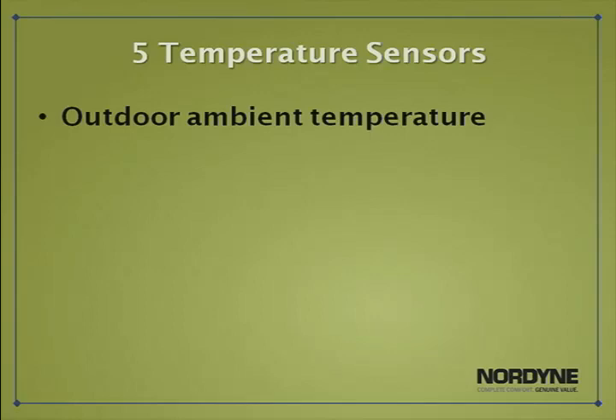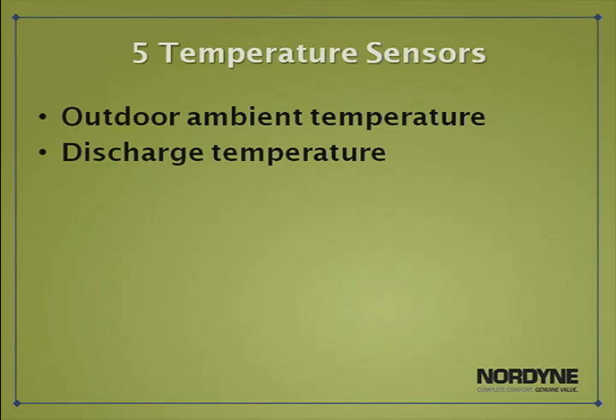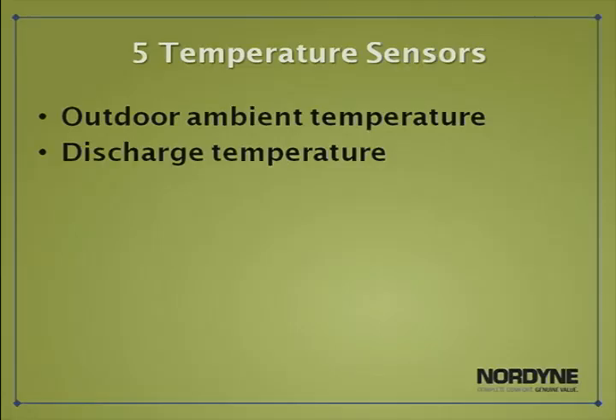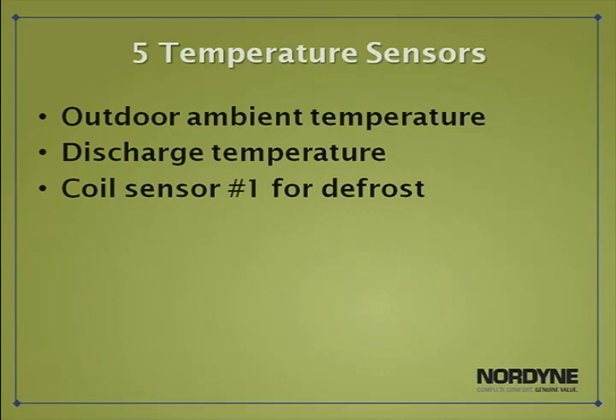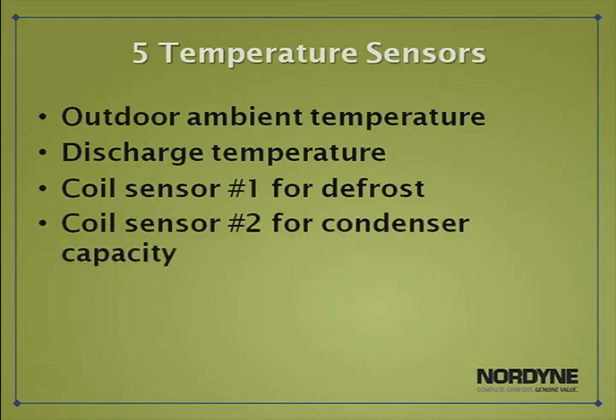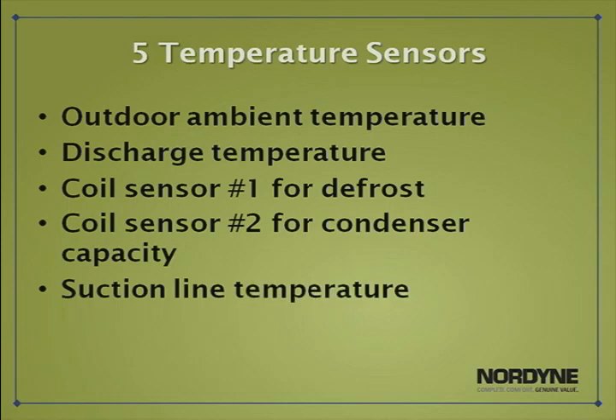The next temperature sensor is the discharge temperature sensor. This is used for compressor override and fault conditions. If the temperature reads 221 degrees Fahrenheit, the unit will shut down and an error code will be displayed. The next 2 sensors are located on the outdoor coil. Coil sensor number 1 is used for controlling defrost. Coil sensor number 2 is used to control the condenser capacity when the system is in cooling mode. The 5th sensor is the suction line temperature sensor.